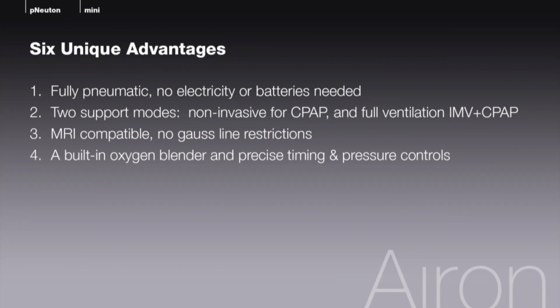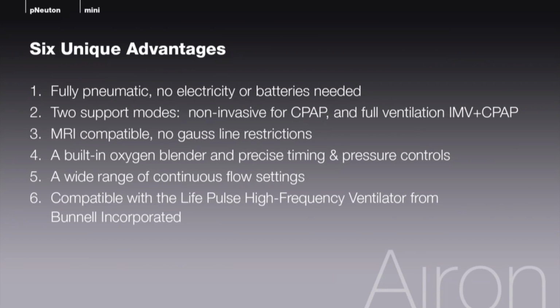A built-in oxygen blender and precise timing and pressure controls to match the complexity of pressure-limited ventilation found in standard infant ventilators. A wide range of continuous flow settings to provide the right ventilation for the size of your patient with the least amount of expiratory flow resistance. Compatibility with the Life Pulse high-frequency ventilator from Bunnell Incorporated, providing conventional ventilation in tandem with the Life Pulse without interfering with high-frequency ventilation or causing nuisance alarms.